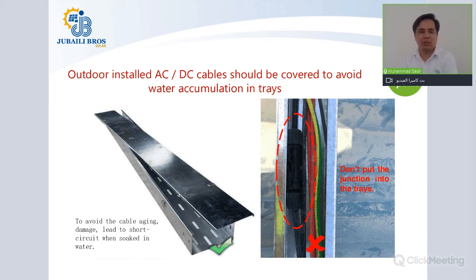Outdoor installed AC and DC cables should be covered to avoid water accumulation in trays. Normally in outdoor installations, it has been seen that people are using trays without a cover. This is not recommended because the sunlight would be hitting your solar cable first thing. In the long run, even a UV rated cable can degrade. Further, water accumulation in trays could damage the insulation of the solar cable, because water when heated can damage anything. Also, you are not advised to have MC4 connection points inside the cable trays, because it will create stress on the adjacent solar panels in the long run and damage the other solar cables as well. So please try to use covers when you're using outdoor cabling, and similarly you should not be using connection points inside the cable trays.